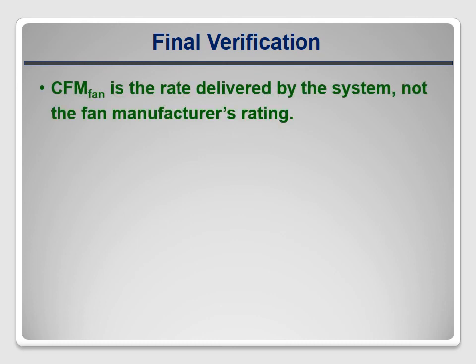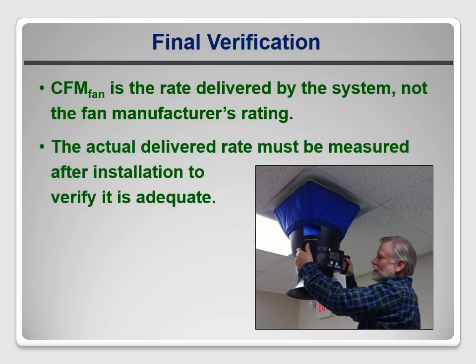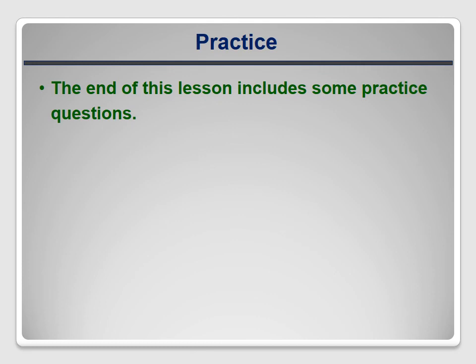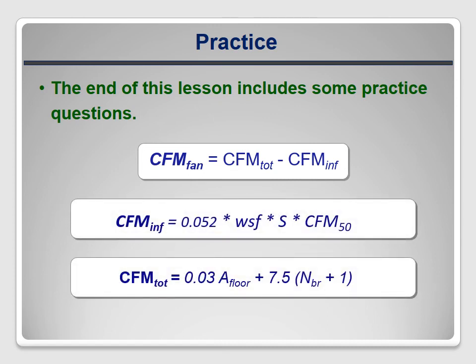ASHRAE 62.2 is very clear that the calculated ventilation rate applies to the final delivered ventilation rate of the installed system, not just the manufacturer's capacity rating for the fan. The flow rate of the installed system must be measured and demonstrated to be capable of meeting the ventilation requirement. To reinforce these calculation methods, we've included some practice questions in this lesson. You'll need to use these three formulas to complete them, and you'll also need them to complete the 10-question quiz at the end of the course.